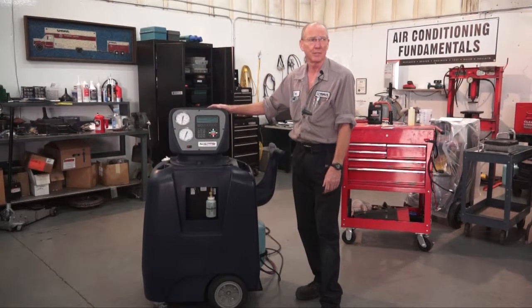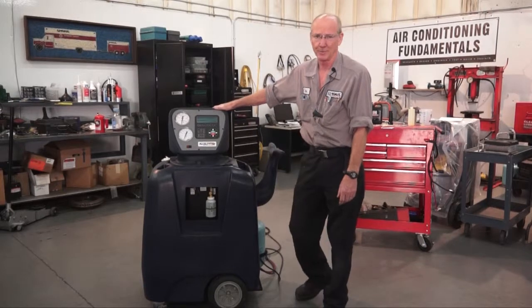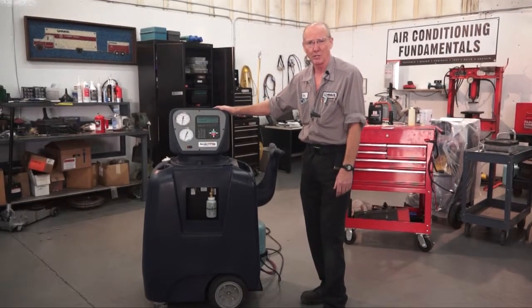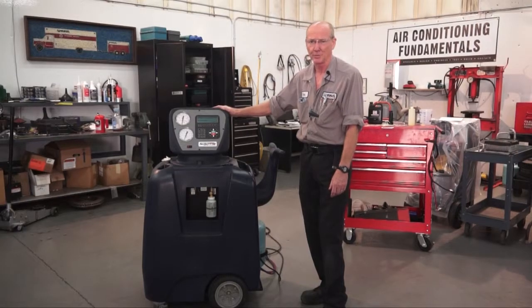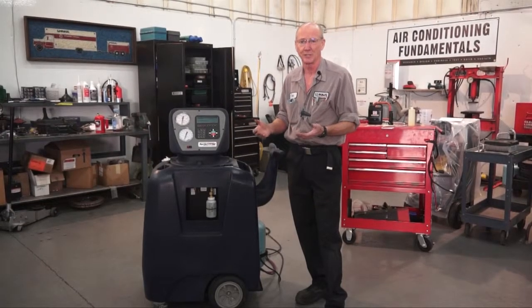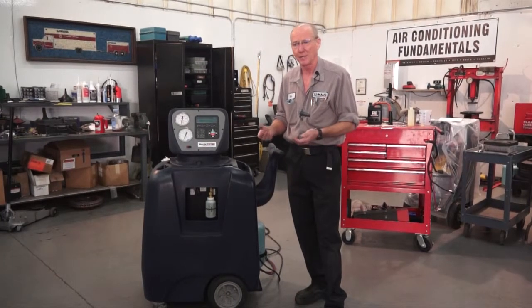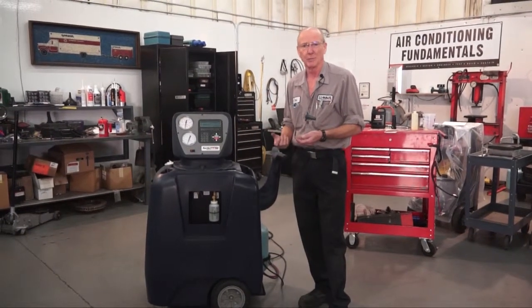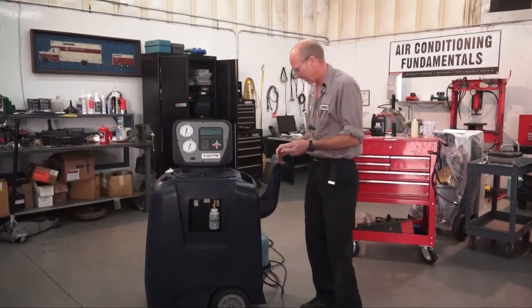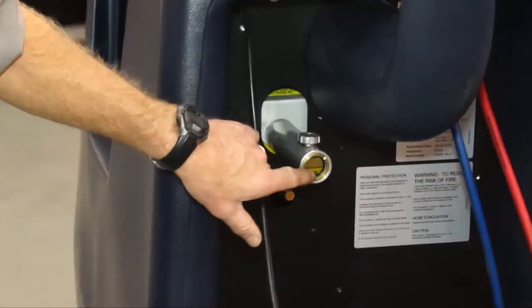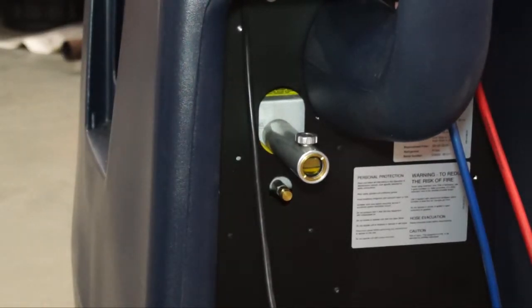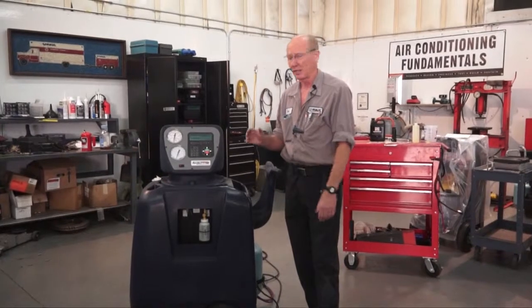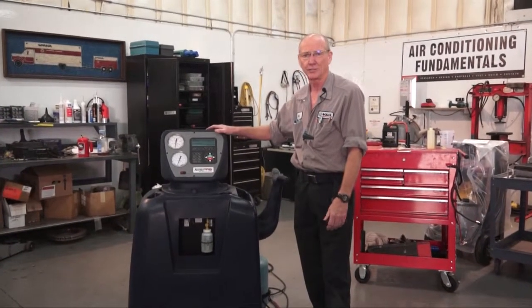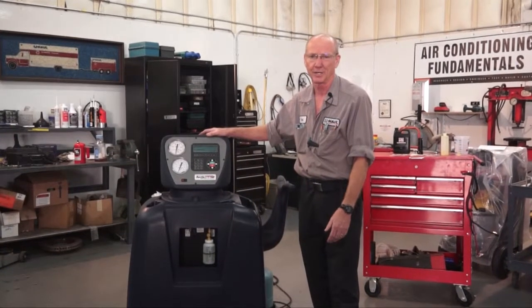First thing I'd like to go through is the vacuum pump oil replacement. Every 10 hours of service, the machine will prompt you to replace the vacuum pump oil. It's very important because, like all oils, they shear out of grade and wear out. The additives drop out of them, especially with a vacuum pump. It'll collect moisture, and you'll notice sometimes that the oil through the sight glass, back here, that monitors the oil level, will get a little cloudy. If you see that prior to the 10 hours, you also want to replace that oil ahead of time.